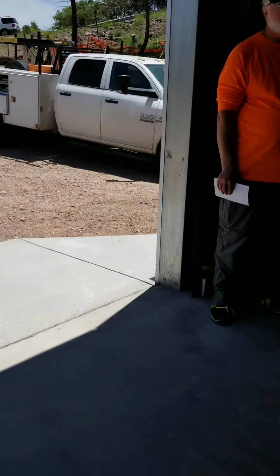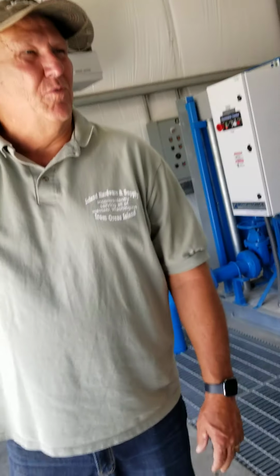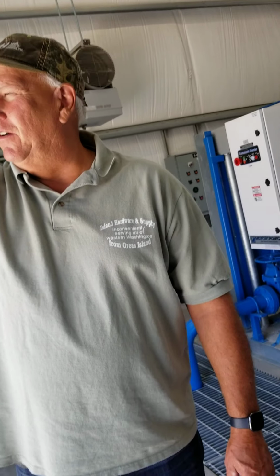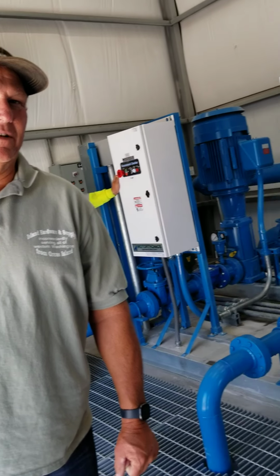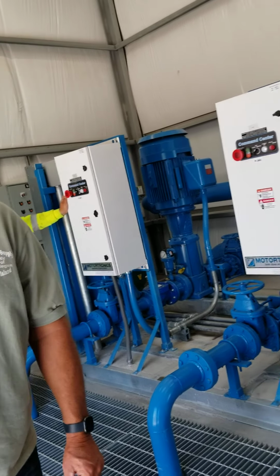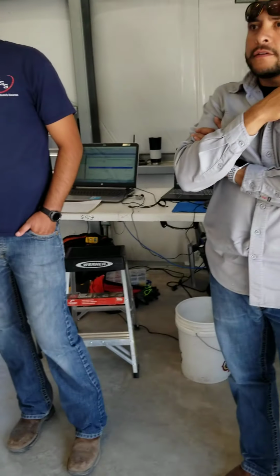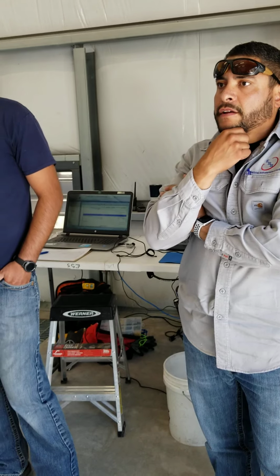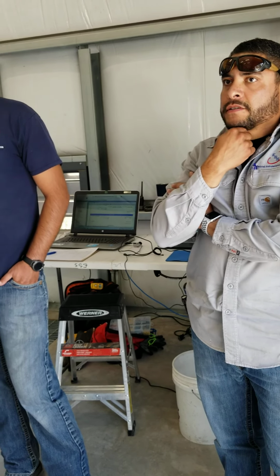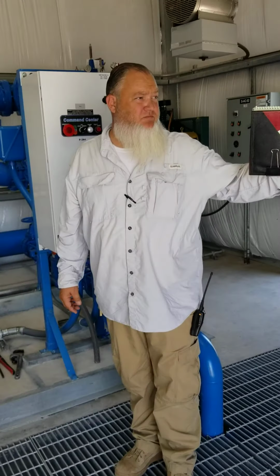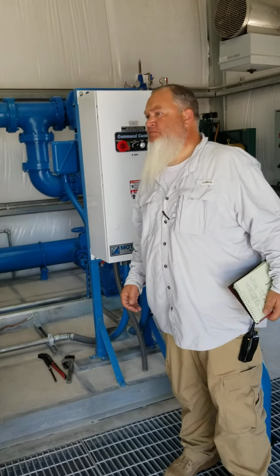And then we've got to keep water in the tank, so we'll do that training, but we've got valves in there for keeping the tanks full. And you can shut down on low level alarm if they run out of water. Have you done that, the high level on the tanks? On a low level? Yes, it does have a low level shutdown on the pumps, so it won't run dry wherever we set those set points. Correct, it'll shut me down over here.